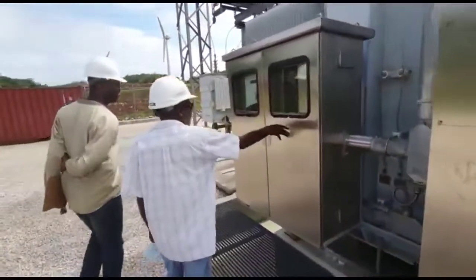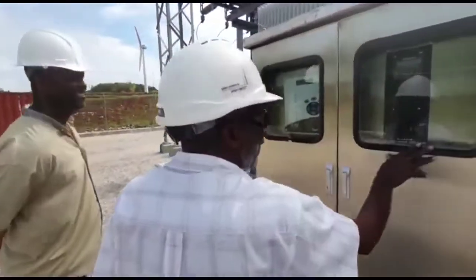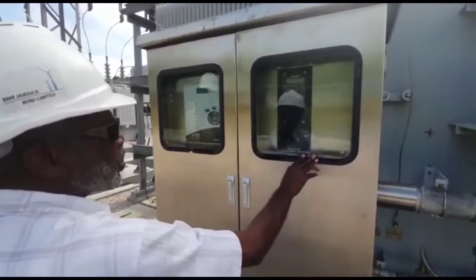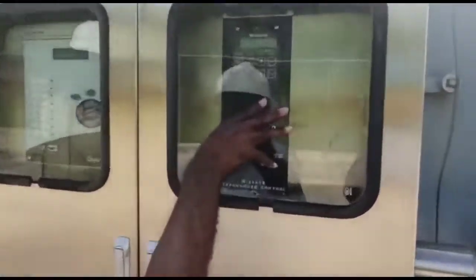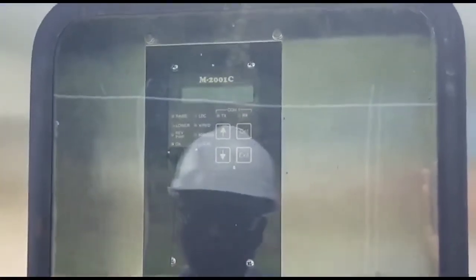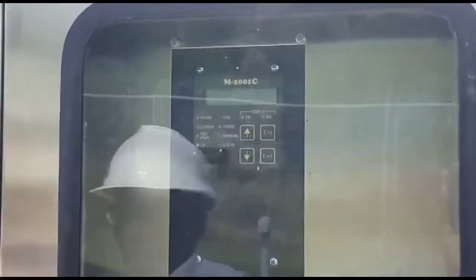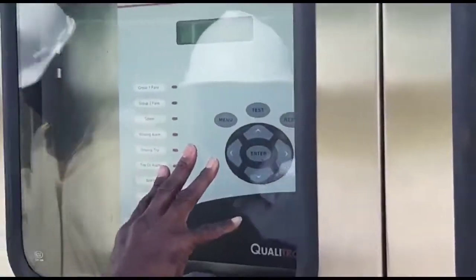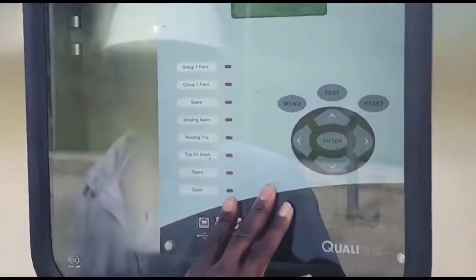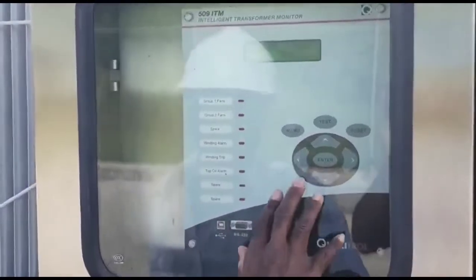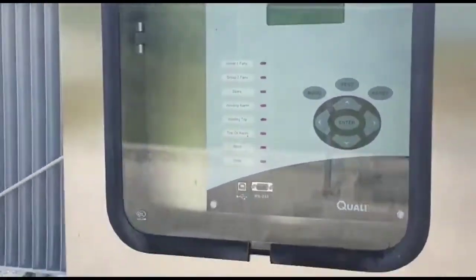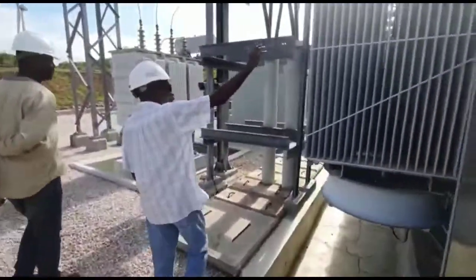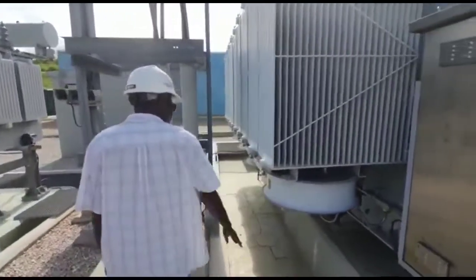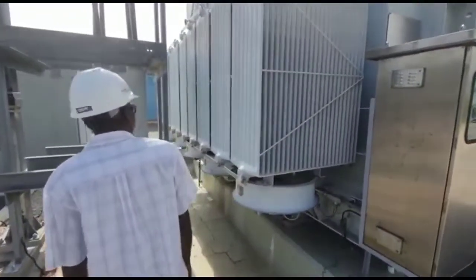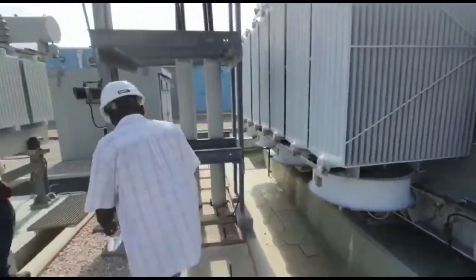On this panel, we have on this side the tap changer controller. This is the unit that sends the signal to the tap changer on the other side to automatically change the setting. And over here we have an indicator that measures the temperature of the oil in the transformer. And for this side, on the low side, we have some more radiators and fans that we use to cool the oil.